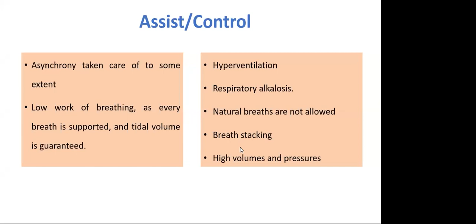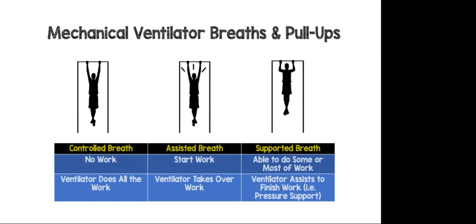So you can remember all these three things like pull-ups. Controlled breath is like you're not doing any work. The ventilator is doing all the work. Assist breath is like you just start some work, and the ventilator takes over and does the full work. Supported breath is where you are able to do some or most of the work, and the ventilator will only support you to finish the work. That is your pressure support. So just remember this: control breath, no work, the ventilator fully does it. Assist, you just start, the ventilator will take over. Support, you have to do some work, the ventilator will support. So these are the basics.